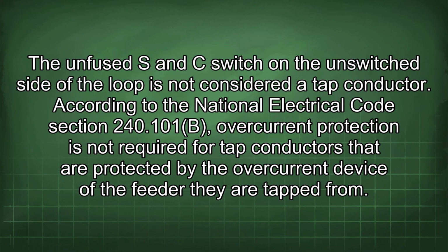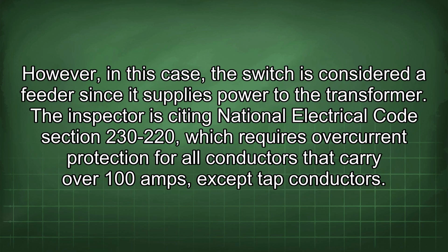The unfused S and C switch on the unswitched side of the loop is not considered a tap conductor. According to the National Electrical Code Section 240.101b, overcurrent protection is not required for tap conductors that are protected by the overcurrent device of the feeder they are tapped from. However, in this case, the switch is considered a feeder since it supplies power to the transformer.